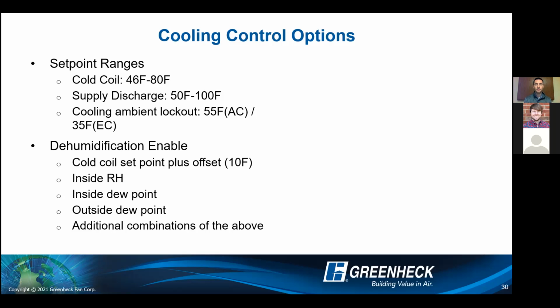And then another interesting fact I wanted to make aware is dehumidification enabled. So obviously when we go into dehumidification mode, that is where we're looking at that cold coil set point, driving to those lower dew points and stripping off all the moisture that we can. So a couple enable set points from factory, the standard sequence will be whatever that cold coil set point is, plus an offset of 10 degrees from the outdoor air temp. That is when we're going to enable dehumidification. So for example, if it's a 55 degree cold coil set point, anytime that it is 65 degrees or warmer outside, that is when we're going to enable dehumidification to strip that moisture off.